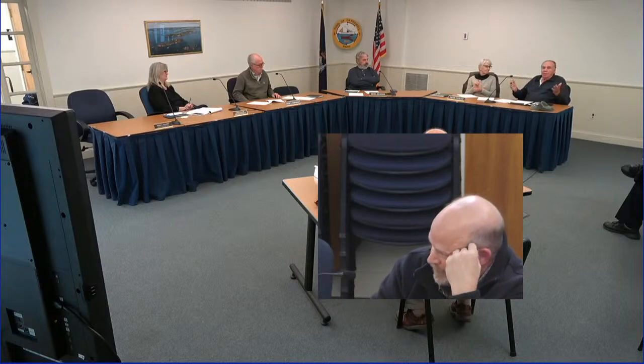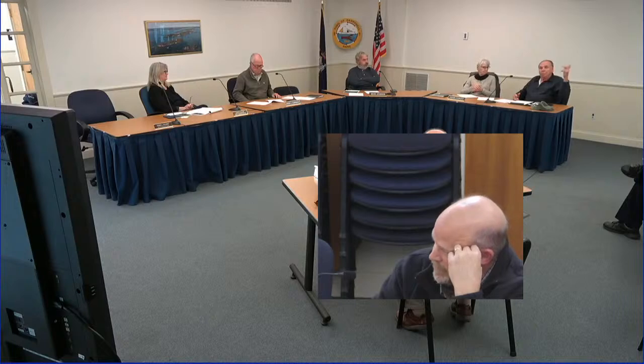Right. And that's not popular for the boiler manufacturers to talk about, but that's how it is. I've got that system in my house. Part of my house is radiant, the other back part's baseboard, with mixing valves and all kinds of contraptions down there. Plumber's nightmare. But that's only for a very small percentage of the time of the year. It's like a bell curve. 60 to 70% of the time, if it needs to run on condensing, it'll run on condensing. But most of that time, we'll be able to be on the heat pumps, except for the auxiliary loops, which is good that we can go down to 10%.